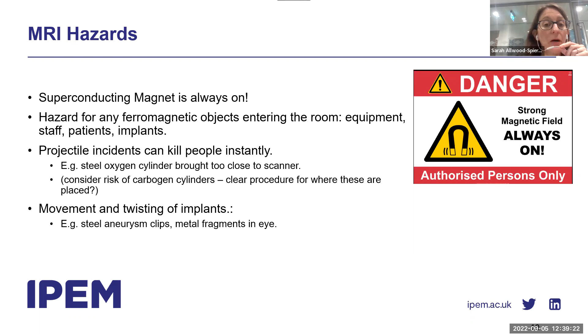During a scan, we're applying these pulse sequences, which are a combination of lots of radio frequency pulses and switching on and off the imaging gradients. And these give us some additional hazards. The RF pulses can cause heating of tissue and a rise in core body temperature. And so the power deposited in the patient has to be limited. And this is limited by the SAR limits on the scanner.